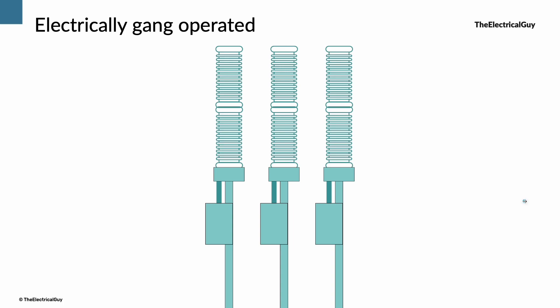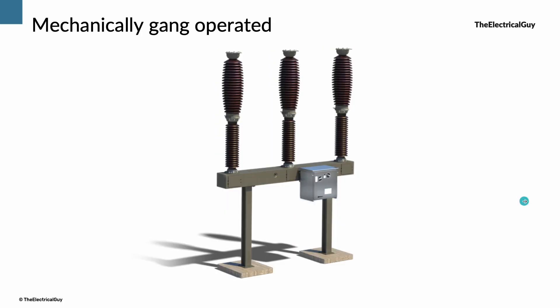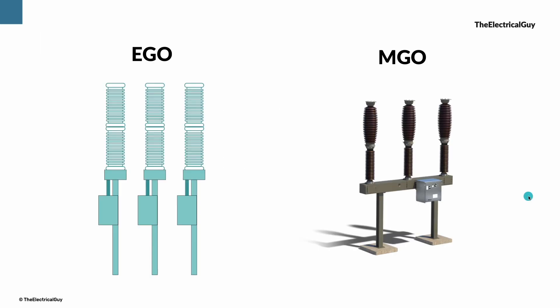If the breaker is mechanically gang operated type, then it cannot perform single phase auto reclosing duty. It can only perform three phase auto reclosing duty wherein all the three phases are reclosed. Let me know in the comment section for which ratings generally MGO type breaker and EGO type breaker are used.